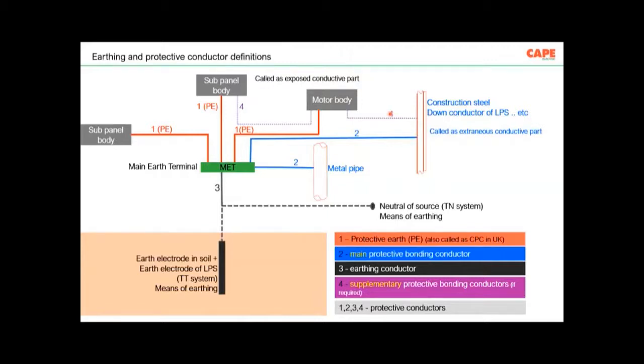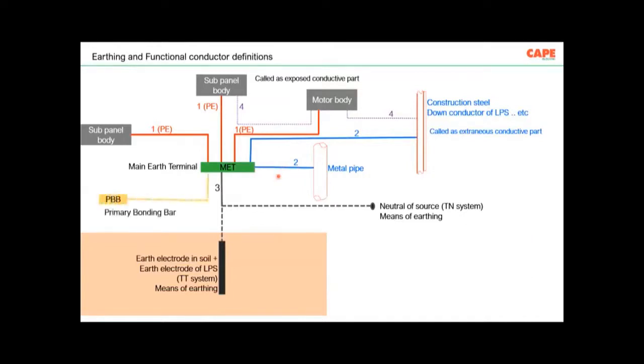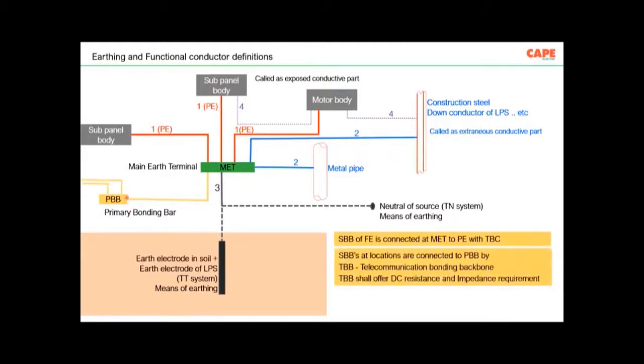You just find out. Now, once we talk about the protective bonding, let us say, for example, this connection number 2, which I am scrolling, the resistance of this wire, the sizing of the wire, the resistance of each joint, all these are important. Now, what about functional earthing? In the previous slide, I have shown functional earthing. All the equipment together, the FE terminals are connected to PBB or SBB. Every building shall have a primary bonding bar, which is for the purpose of functional earthing. The PBBs are connected to SBB, like sub bonding bar, and these wires are called telecommunication bonding backbone. Anyway, I don't explain this much because this is a little bit tricky to understand.